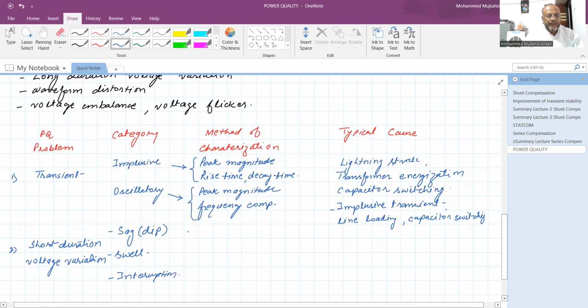Interruption. So sag is measured in magnitude. The method of characterization is magnitude and duration, that is, how many cycles the sag is present. Similarly, swell is also measured in magnitude, how much rise in voltage, whether 0.1 pu, 0.2 pu, 1.1 pu, and so on, and the duration the sag or swell is present. For interruption, it is the duration: how much time there is an interruption in the power supply.